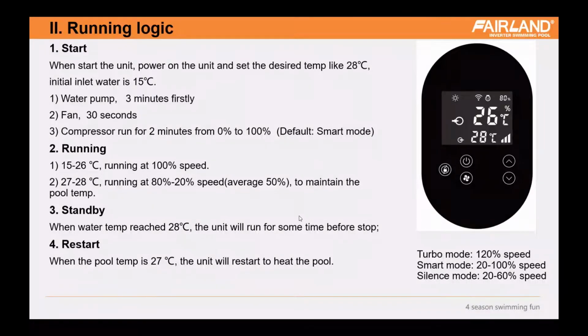And part two is running logic. When you power on the unit and press the power button to start it, you press the up arrow button to set the desired temperature, like 28, and assuming the initial inlet water is 15. So the water pump will firstly run 3 minutes, and after 3 minutes of the water pump running, the fan will start to run.